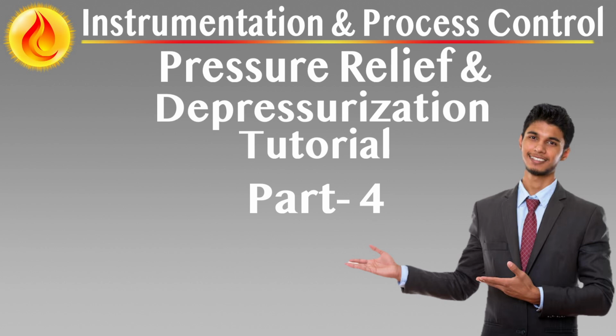Flame monitoring and alarming. Each pilot must be monitored using a robust K-type thermocouple capable of withstanding direct flame and radiation exposure. Failure of any pilot must generate a control room alarm with clear identification of the affected pilot. Thermocouples should be properly insulated and supported to prevent failure under thermal stress.